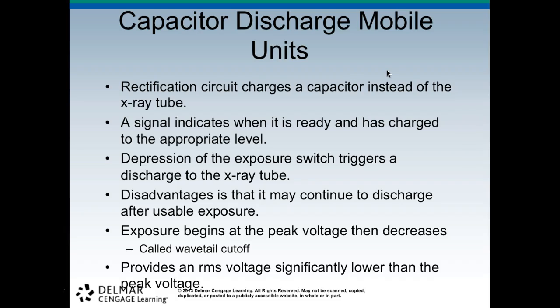So you depress the exposure switch and it triggers a discharge of the X-ray tube. The disadvantage is that it may continue to discharge after the usable exposure. So that's not good. Exposure begins at the peak voltage and then decreases. It's called wave tail cutoff, and it provides an RMS voltage significantly lower than the peak voltage.